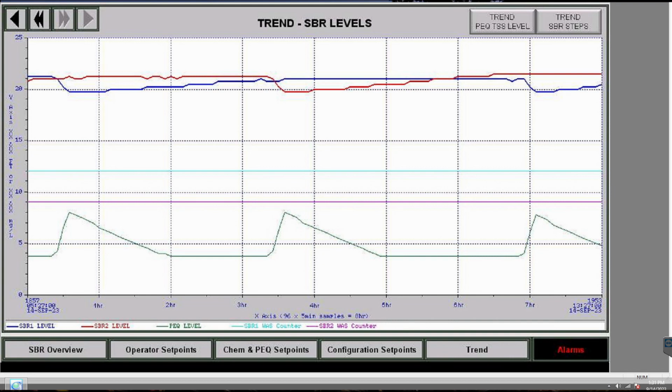Because I know you're saying it's fluctuating all the time, and that makes sense when it's in between the bottom water level and the top water level. But whenever the sluice gates are just opened up and there's some water backed up, to the SBR it thinks it's a storm. It seems like the pumps just stay off. Yeah, the pumps never shut off in that scenario, right? So they just keep running and keep running. So that average of the flow percentage, instead of going down every now and then, just keeps going up, up, up. And something then triggers that to go to that 23.